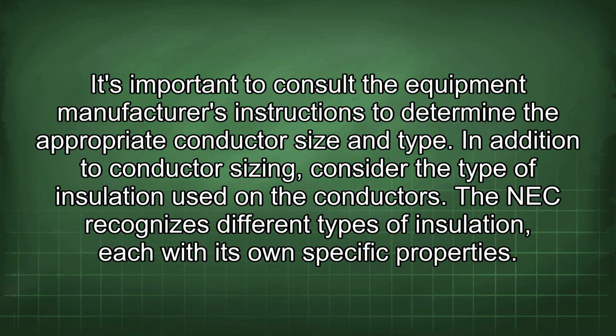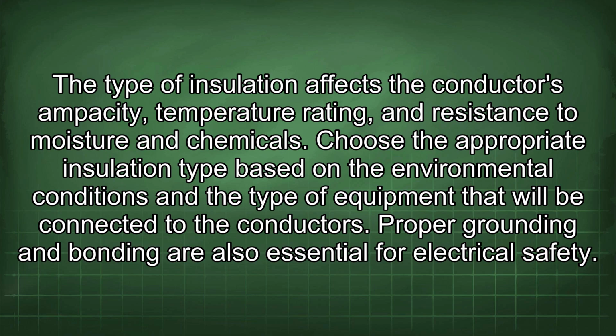In addition to conductor sizing, consider the type of insulation used on the conductors. The NEC recognizes different types of insulation, each with its own specific properties. The type of insulation affects the conductor's ampacity, temperature rating, and resistance to moisture and chemicals. Choose the appropriate insulation type based on the environmental conditions and the type of equipment that will be connected to the conductors.